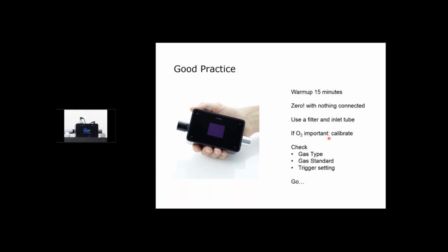This brings me to the summary. What have we done? Before every measurement, or when we take CITREX into operation, we have a warm-up of 15 minutes. Then after removing the covers, we perform the zero. Nothing else should be connected either. Then we use a filter and an inlet tube. Oxygen sensor calibration is less important. We do it just before important measurements or once a week. And before every measurement, we should check gas type, gas standard, which should match up with my ventilator, and trigger settings, which should match up with the measurement I want to have.